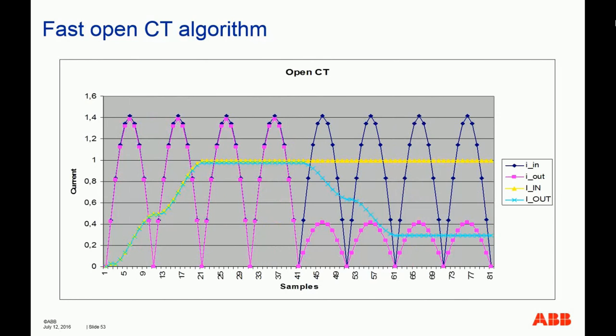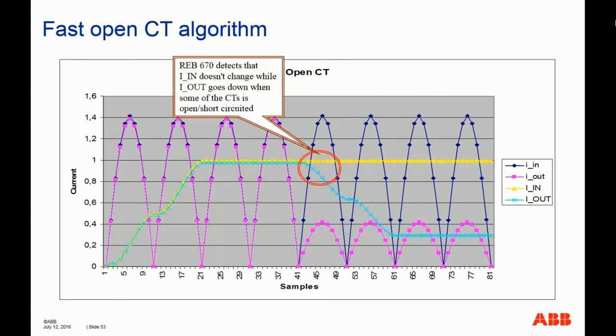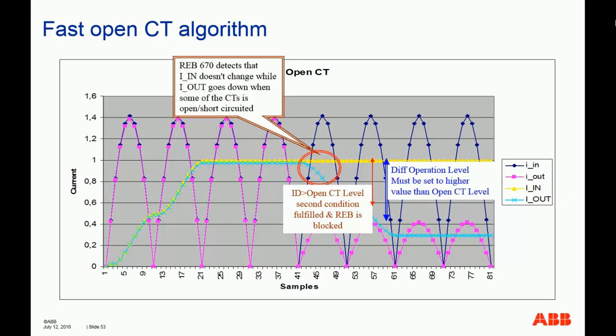So it depends on the settings. In our relay, we have different settings that you can set to tell the relay what to do, either to block or to alarm or to trip, or it depends. Because an open CT could cause an overvoltage problem. It's a risk to field crew. So sometimes you would like to trip. So here are some explanations. The relay detects that the input doesn't change while the output goes down. Okay, so you determine that it's an open CT or short circuit CT. If the resulting differential current is higher than the open CT level setting, the IED is blocked, or does whatever you instruct the relay to do.